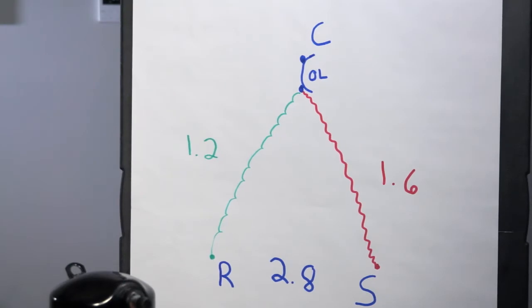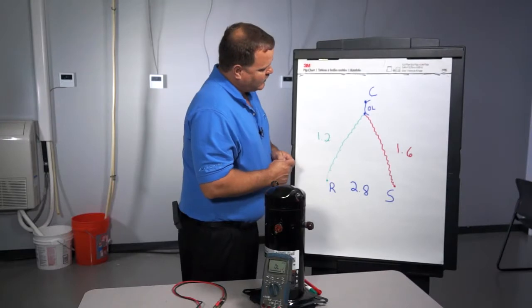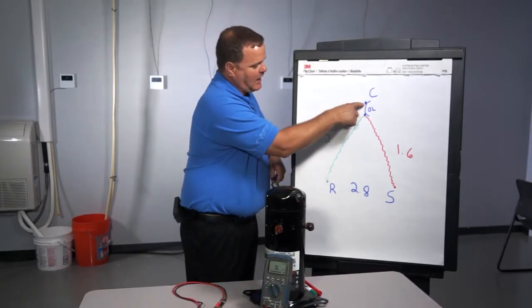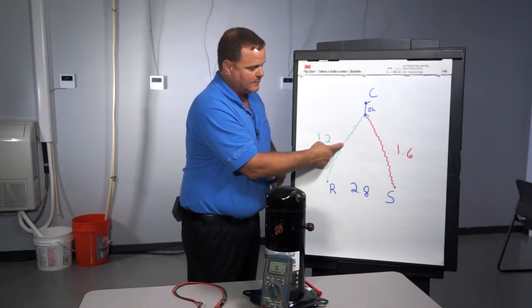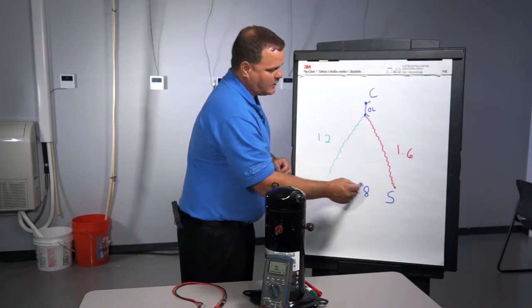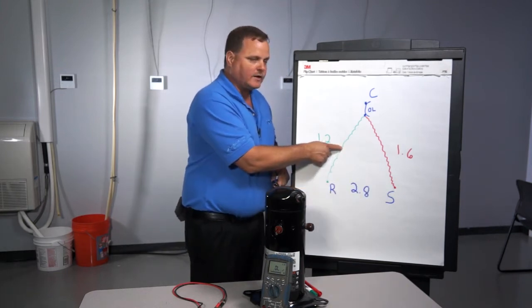So now if this compressor had an open winding, let's say it had an open run winding, then what would happen there is you would no longer get a reading between run and common because this winding here would be broke. And then you would no longer get a reading between run and start again because this winding would be broke.